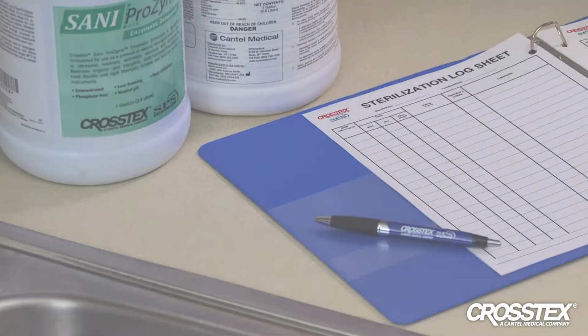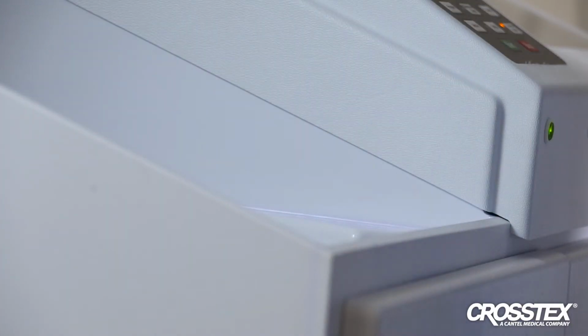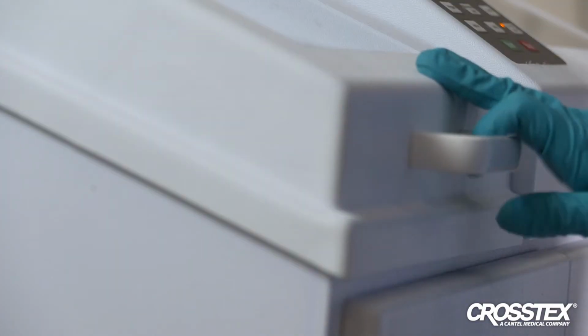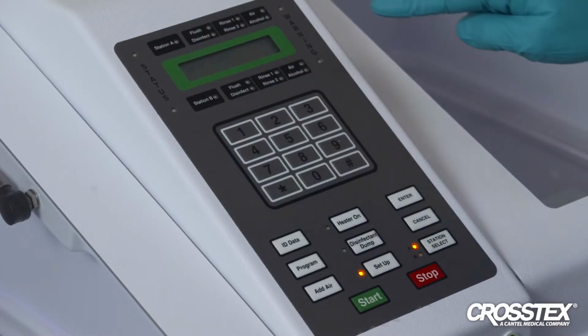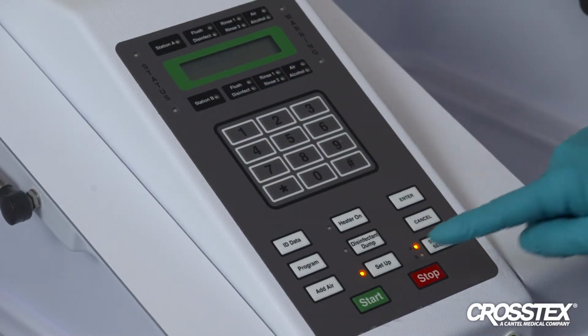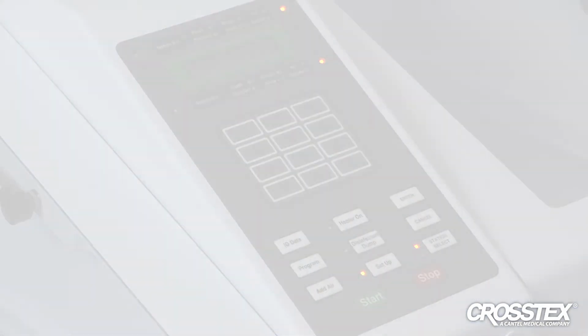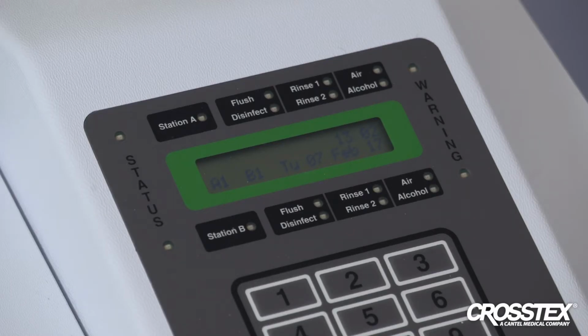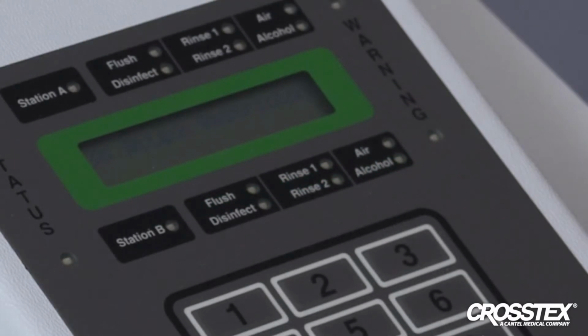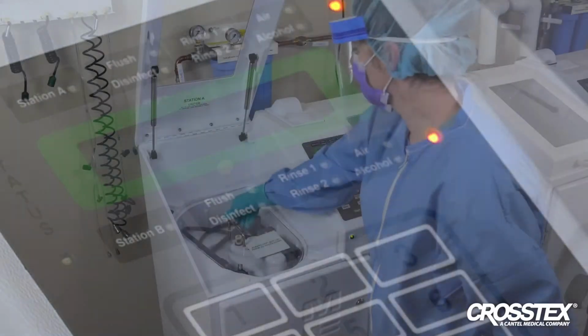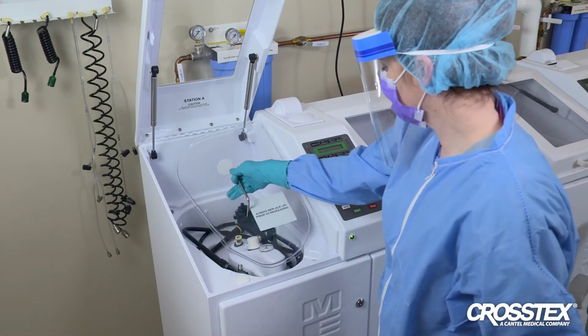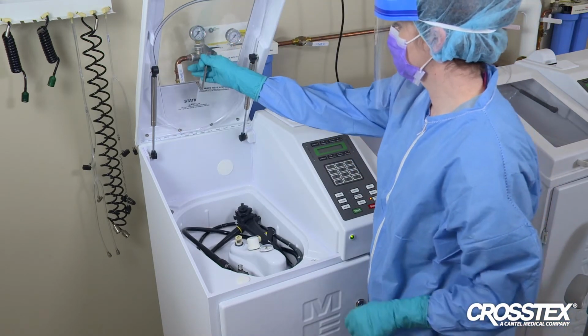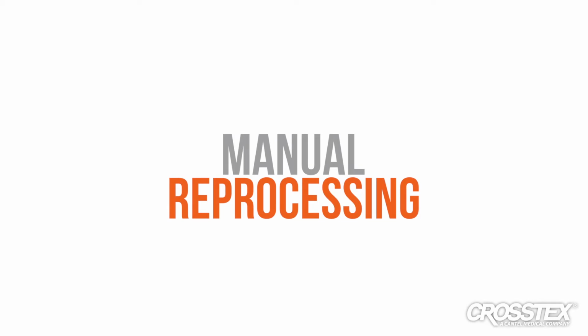To run the reprocessing cycle, close the lid and secure. Select the appropriate cycle and select Start to begin. Perform the automated disinfection cycle in accordance with the AER manufacturer's IFU. Be sure to select a cycle that has been validated for use with OPA-based disinfectants and the scope manufacturer's IFU. When the cycle is complete, verify that the stop LED is illuminated before opening the lid and removing the scope. Now, let's review how Rapicide OPA 28 HLD is used in manual reprocessing.